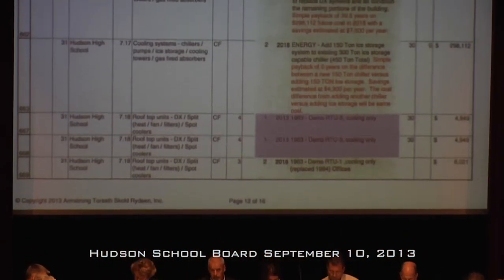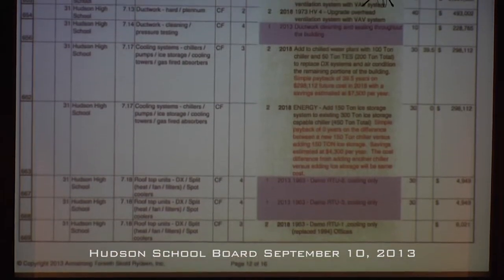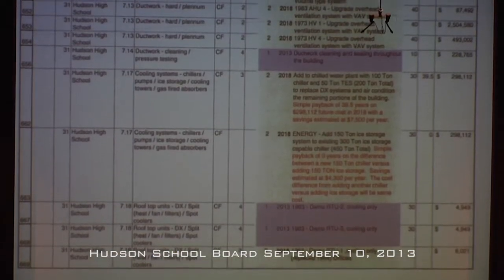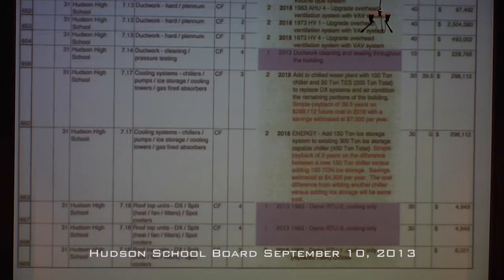If you wanted to cool your entire building, we would add another 150 tons of ice storage and another 100 tons of chiller. So you'd end up with about 600 altogether, 650 tons of cooling. So that would upgrade your existing cooling system and cool the rest of the building with chilled water.